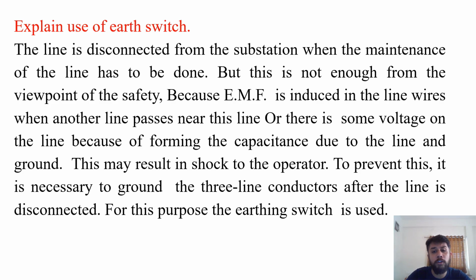This may result in shock to the operator. To prevent this, it is necessary to ground the three line conductors after the line is disconnected. For this purpose, earth switch is used.